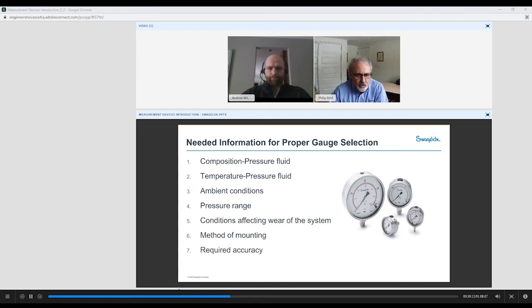So with that, a few things before we take some questions. It is important to note when you're going to select a gauge, you want to know the composition of the fluid you're measuring, the temperature. What are the ambient conditions? Is it in a corrosive environment? Is it in a hazardous environment, a dark area? You may want to get a reflective lens in the back of this, which is available as well. You want to know the pressure range, and remembering that you're most accurate in the center third of that gauge. So if we were trying to measure 100 psi-G, I would select a gauge 0 to 160, typically.